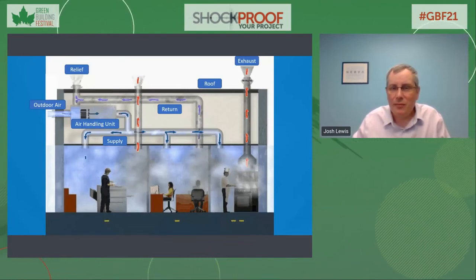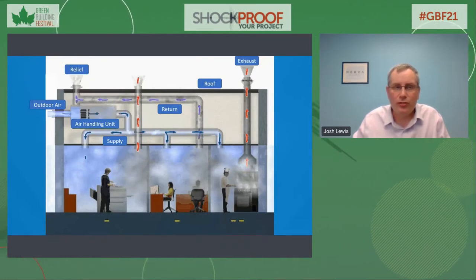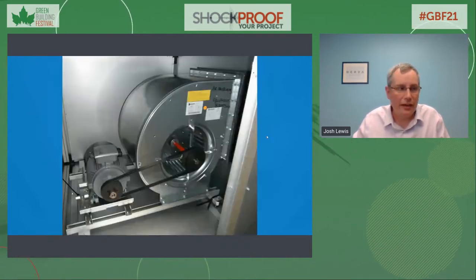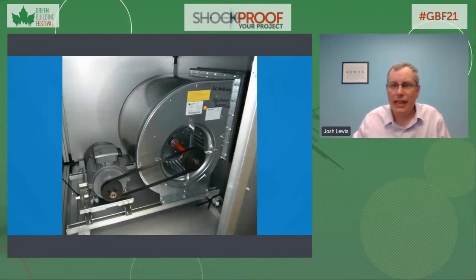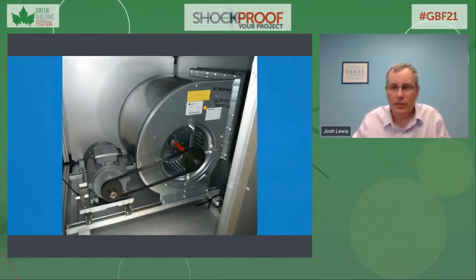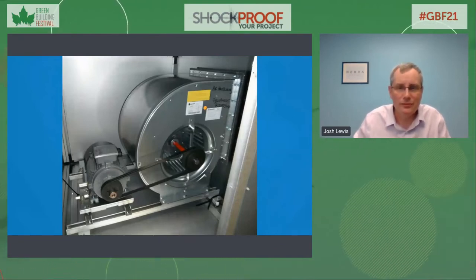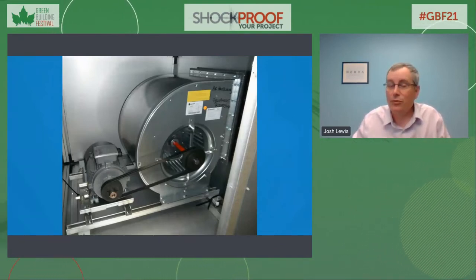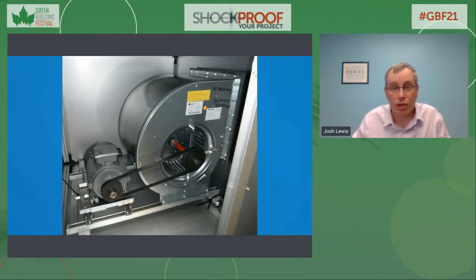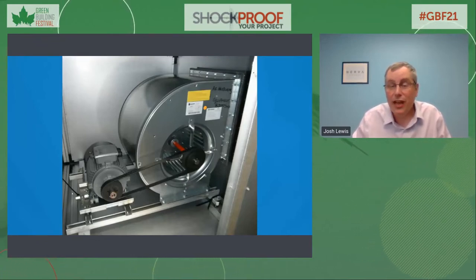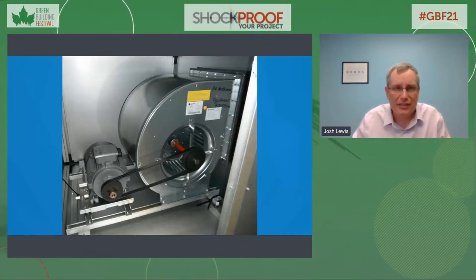Specific actions that have been implemented to keep air moving usually start with ensuring that the HVAC system is running in fan-on mode, meaning that during the hours of the day when the building is occupied, the fans are running constantly to push air in and around the building. You might ask yourself, isn't that how HVAC systems are supposed to work? Well, not necessarily. If you think about the furnace most of us have in our homes, often it is set to fan auto mode, which means that the fan only turns on when there is a call for heating or cooling. If the temperature set point has been satisfied, then the fan is stopped, as is the air circulation. While this is energy efficient, it has a negative impact on indoor air quality.